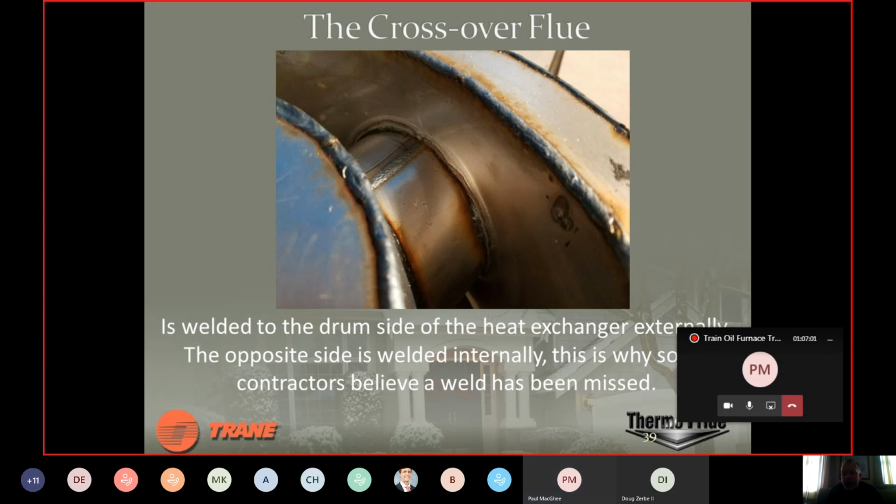Yes. And really, the one thing that I wanted to elaborate on there is I used to tell guys, for example, that low profile high boy furnace is down about 1 inch, lift your coil 2 inches. And it's really not the case. You have to look at each application. And like I said, on your low boy furnaces, I see a lot of them out there that the coils are setting right on top. And I've never had a situation yet where I've heard of any of these coils melting, the high temperature coil. So as long as you're using the ones that Trane here has spec for you, the high temperature coils, you know, the 3 inches is the point of contact. That's the clearance that we're looking for.